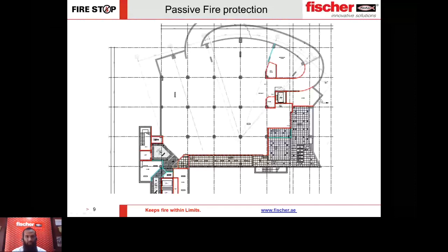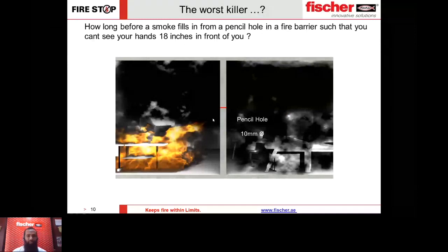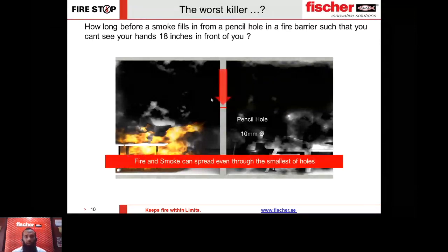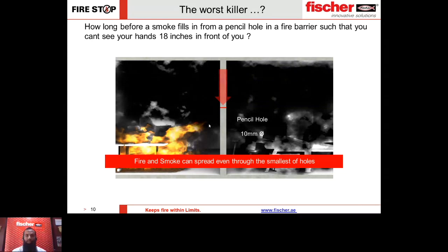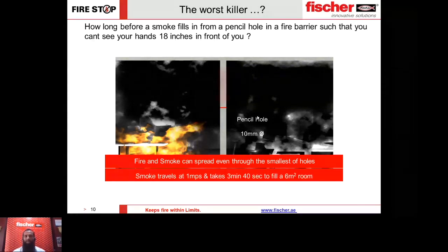Imagine there is a fire, and that fire fills up the fire side of the barrier. Can you guess how long it would take for smoke to pass through that small pencil hole such that you cannot see your own hand 18 inches in front of you? Smoke travels at a speed of 1 meter per second — it would take just 3 minutes 40 seconds to fill a 6 square meter room full of smoke from that 10 mm pencil hole.